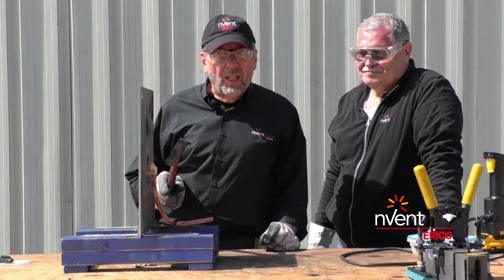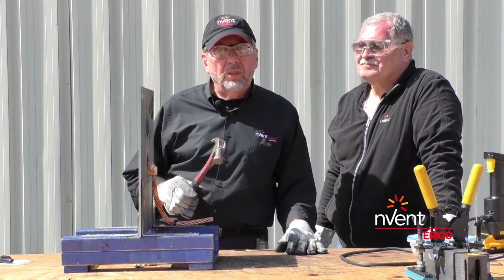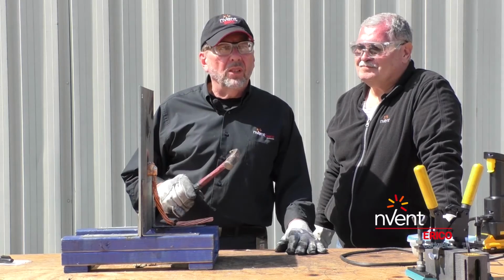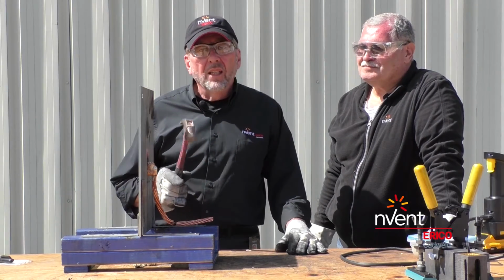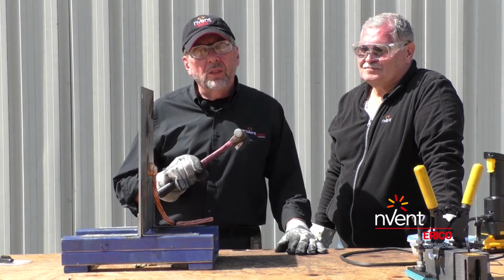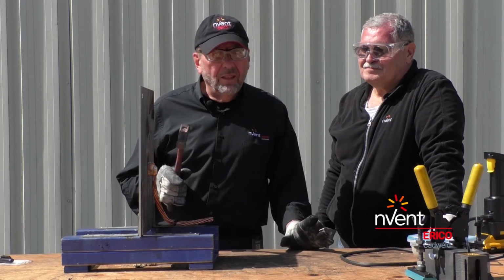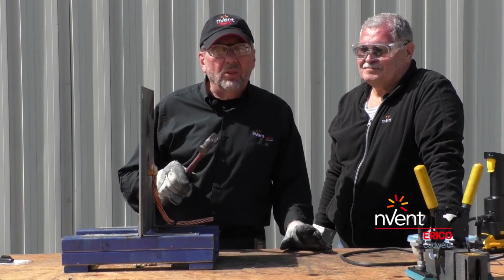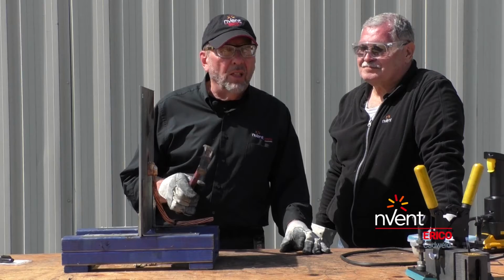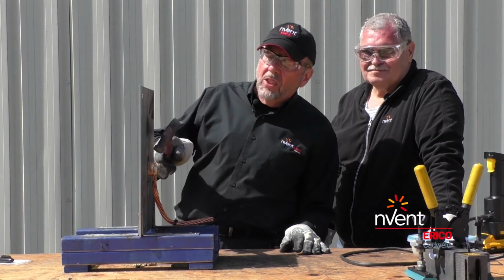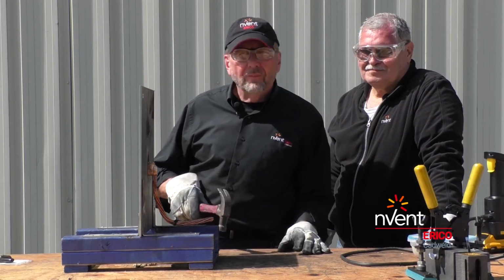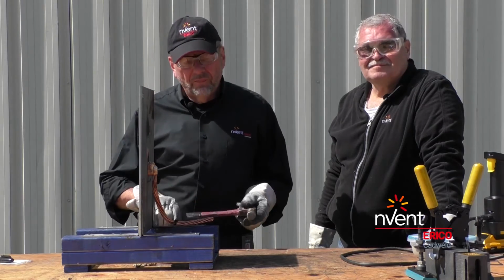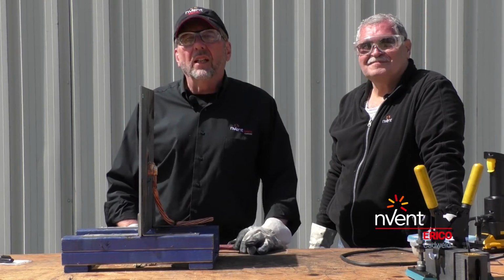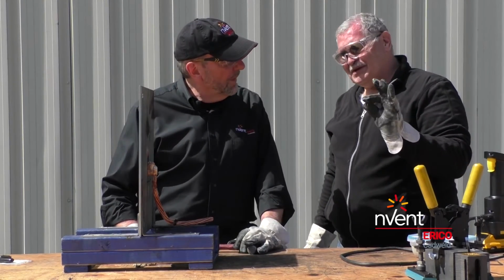If something is wrong, if we haven't cleaned the surface properly, or the cable was out of position, or something was wrong, that light tap will yield the result of the cable coming off, or the connection coming off the steel surface. So all we have to do is that, and our work here is done.